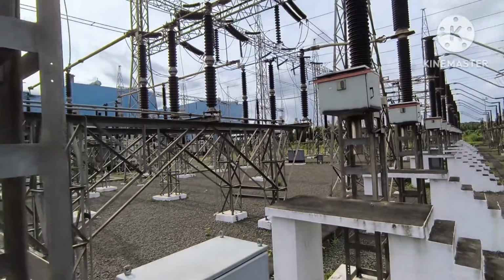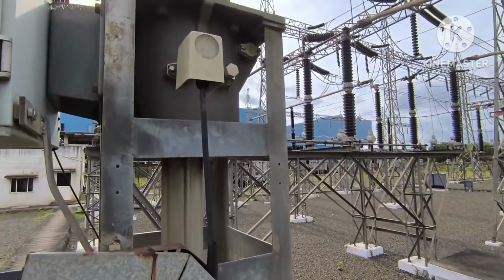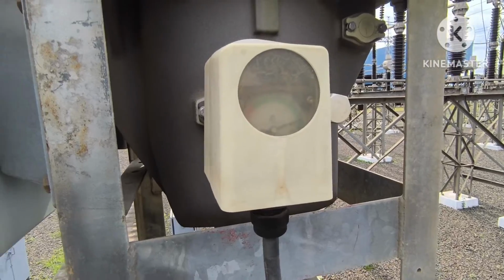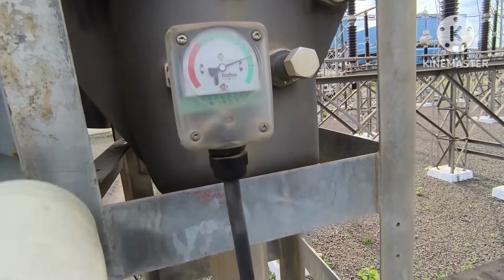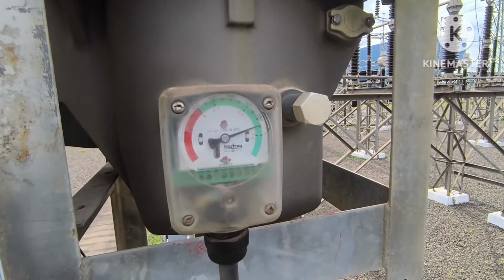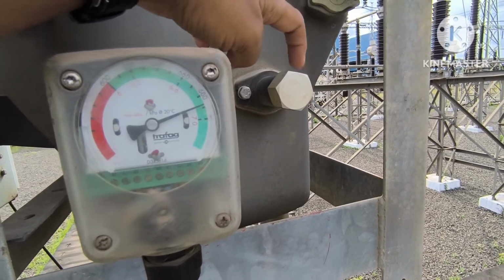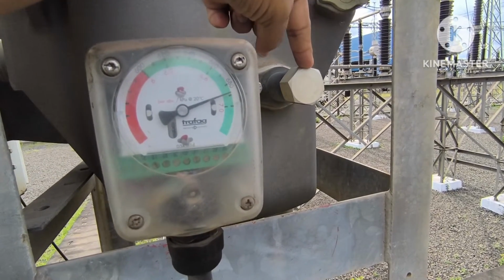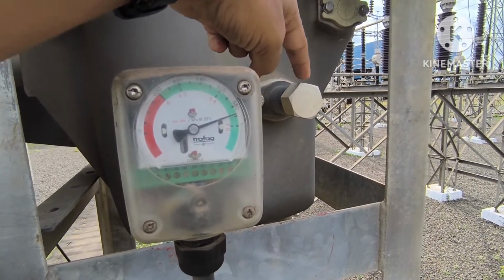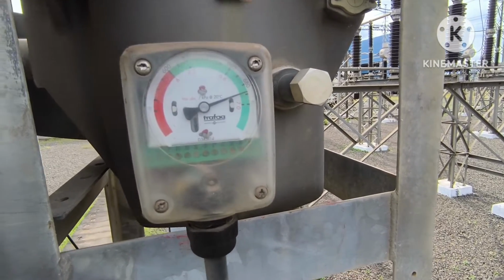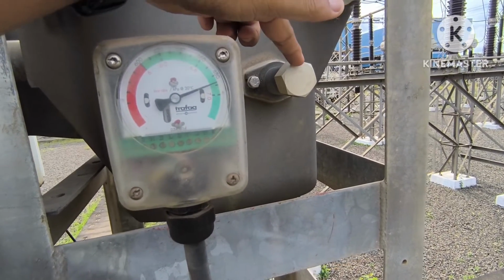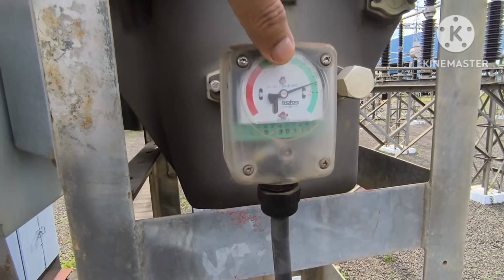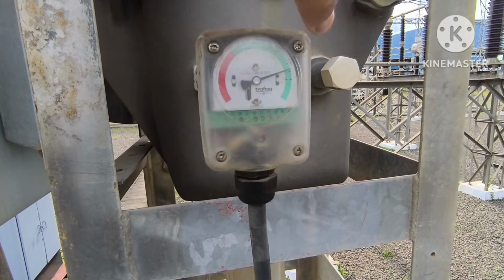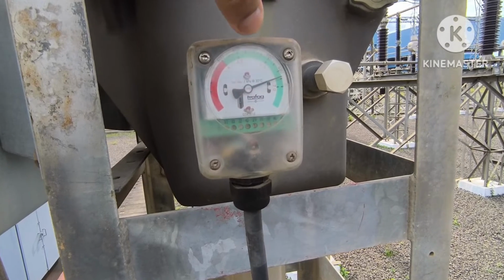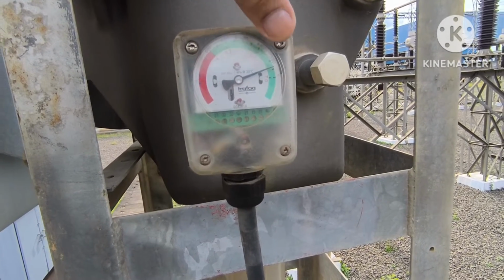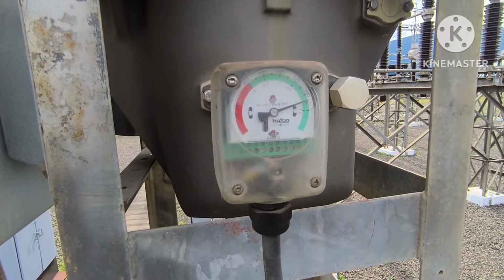Now we'll see the gas monitoring device for this breaker. This is the gas monitoring device, and for any gas leakage we use the gas filling kit. Using that kit we have to refill the gas here, either at commissioning time or whenever there is a leakage of SF6 gas. The all green zone is called the safe zone. That means whenever the pressure is maintained above 6.2, we can do normal operation.